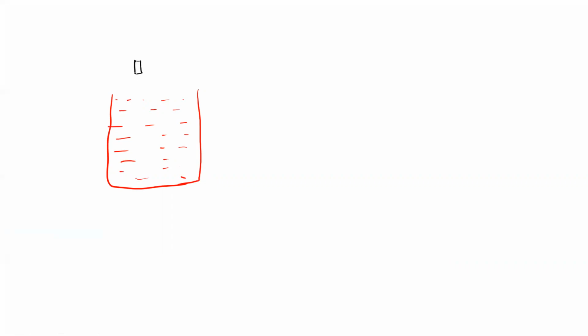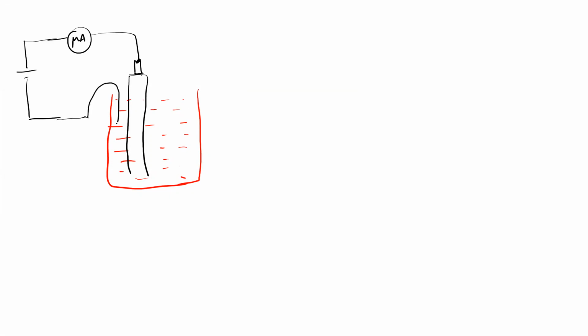One approach could be to use saline water in a chamber. Saline water can conduct electricity, so if the cable is placed in that chamber - suppose this is the conductor portion and this is the insulating material - then one terminal of the ammeter can be connected with the inner conductor. Then we'll have our voltage source, and the circuit can be completed by placing a metallic contact in the water, so that the current passing through the insulating material can be collected by the water, establishing a path for the current to flow.